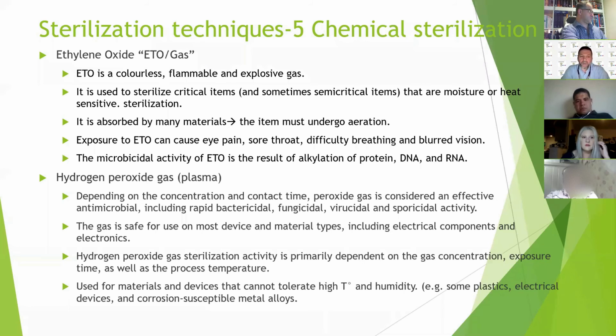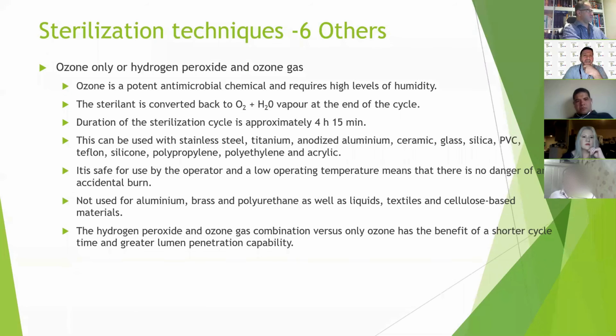Hydrogen peroxide with plasma is as effective as the other one, and it is used usually for electrical components. Last one is ozone, or hydrogen peroxide with ozone. It breaks down into oxygen and H2O by the end of it, and the duration of the cycle is about 4 hours and a quarter. It is used for many, many materials, but it's not used for brass, aluminium, liquids, textile, and cellulose.